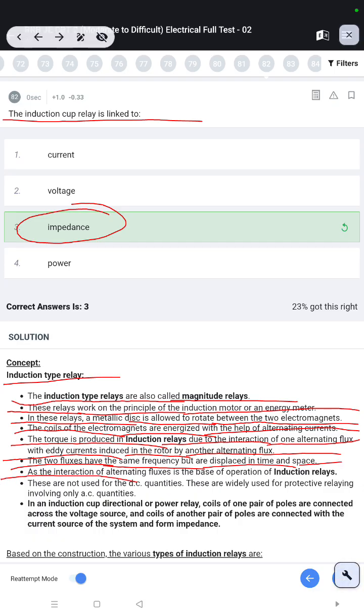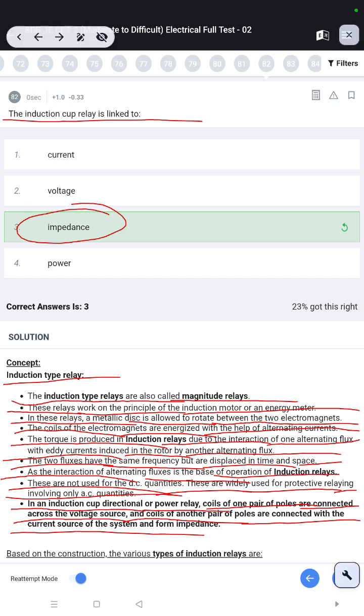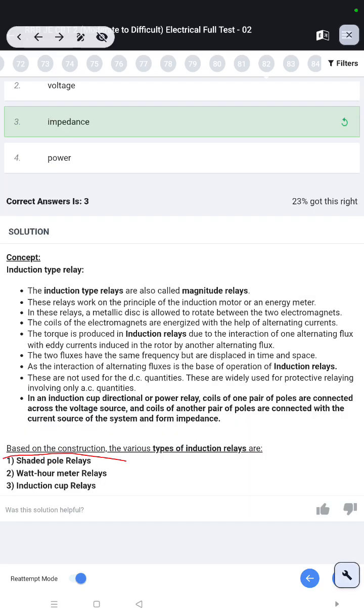As the interaction of alternating fluxes is the basis of operation of induction relays, these are not used for DC quantities. These are widely used for protective relaying involving only AC quantities. In an induction cup relay, the coils of one pair of poles are connected across the voltage source, and the coils of another pair of poles are connected with the current source of the system and form impedance. Based on the construction, the various types of induction relay are shaded pole relays, watt-hour meter relays, and induction cup relays.